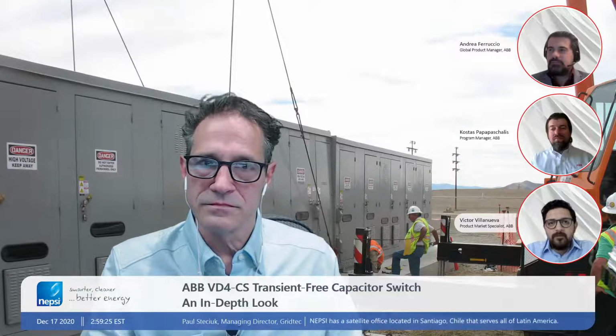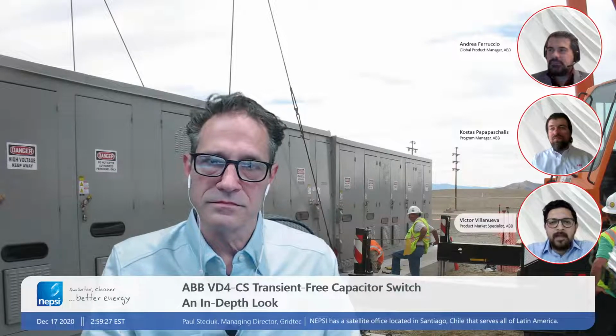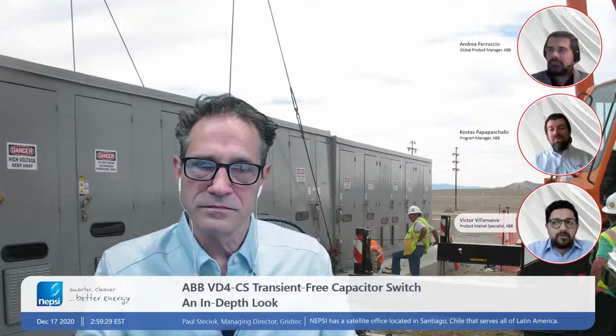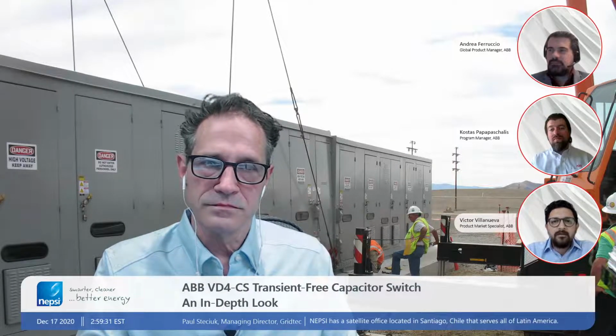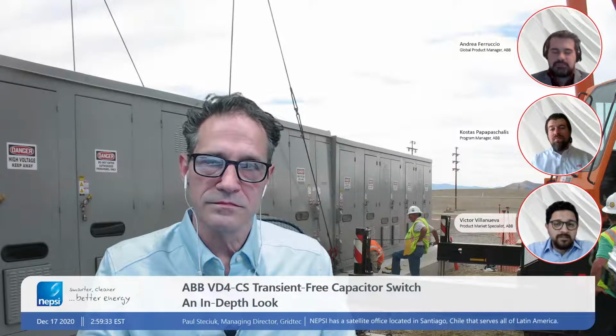One thing I wanted to add, Paul, is that the VD4-CS is a switch and a breaker as well, with a 31.5 kA rated breaking capacity. By having that, in some applications you might have a feeder breaker feeding the cap bank, and you might be able to eliminate it because you already have a breaker within this unit. So that right there is a huge cost savings.